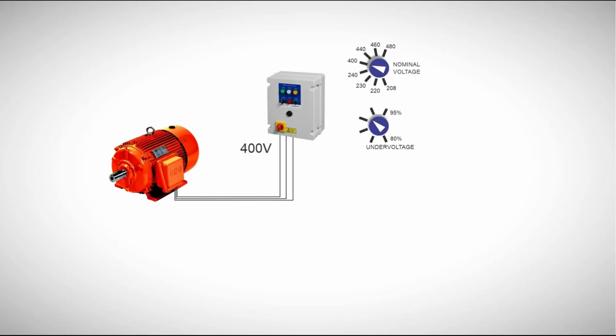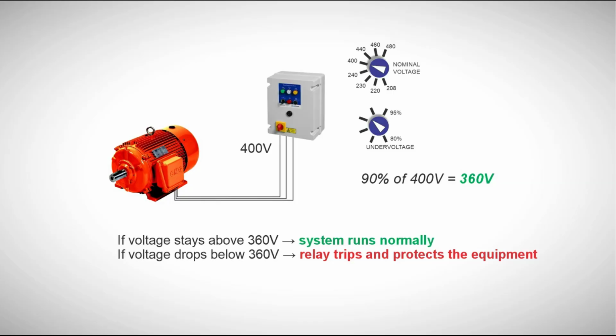Imagine your system is running at 400 volts, a very common industrial voltage, and you set the nominal voltage to 400 volts, and your undervoltage knob is set to 90%. The relay will calculate as 90% of 400 volts equals 360 volts. So, if voltage stays above 360 volts, system runs normally. And if voltage drops below 360 volts, relay trips and protects the equipment.